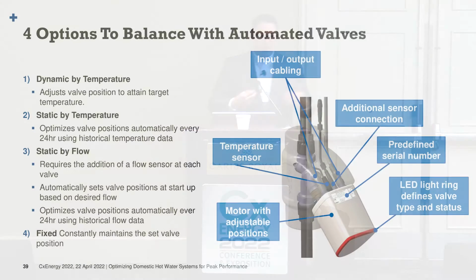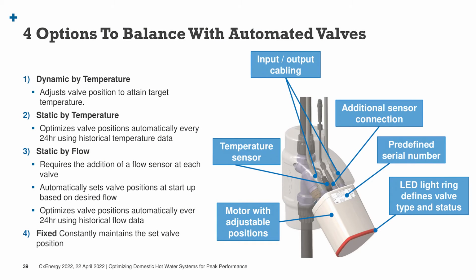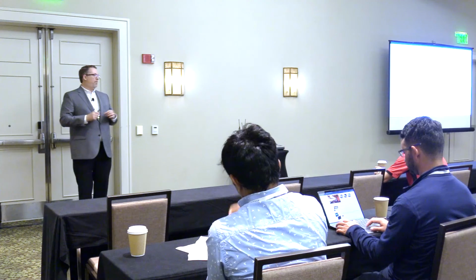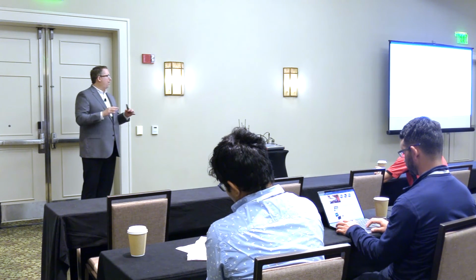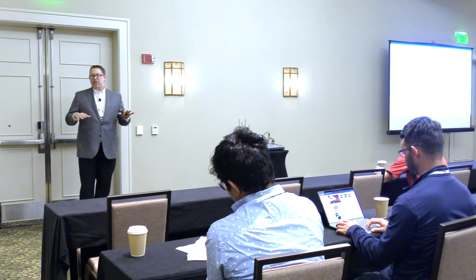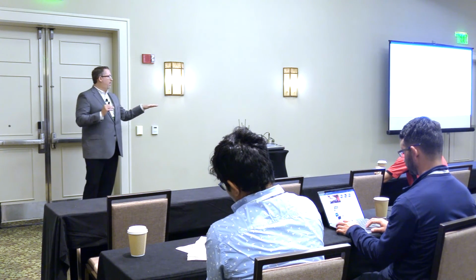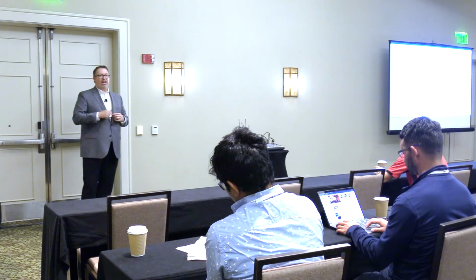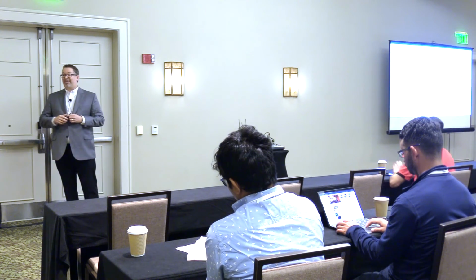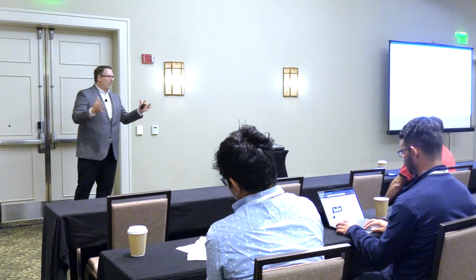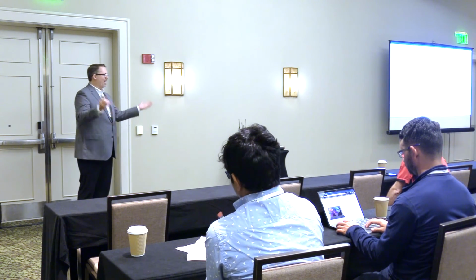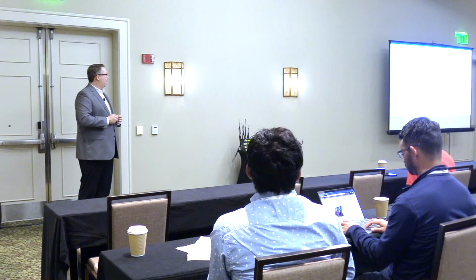With automated valves, you also have multiple choices in how to balance your system. You can do it dynamic by temperature. In that, you set at the control panel the desired return temperature that you want. The system and those valves then dynamically adjust to hit that temperature throughout the day, thus maintaining a consistent temperature throughout your building. Your TAB report is really simple. You just go and export that report. Now you can turn it in to the engineers and say, hey, the system's balanced. It makes your job easier.